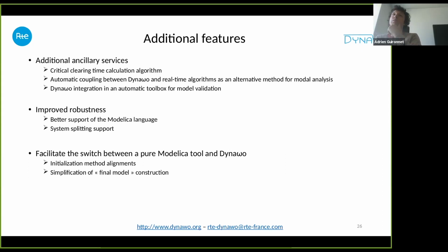Also, coupling the simulation tool with real-time algorithms used for modal analysis, to provide a different approach to modal analysis than linearization, where a lot of questions are open on the way you linearize, for example, saturations and so on. And also introducing Dynawo into an automatic toolbox for model validation, where you compare the simulation results with measurements that you can have in the field, and so try to identify the parameters that are not accurate enough.